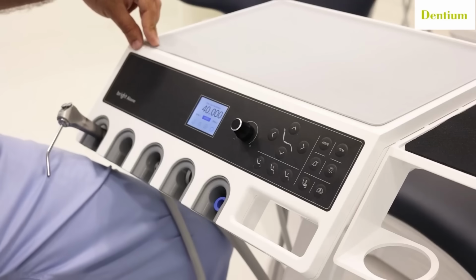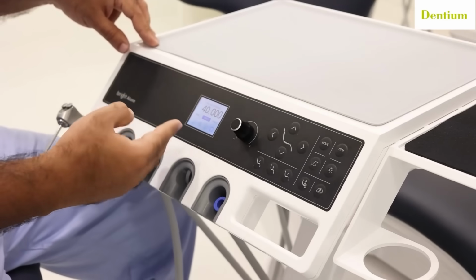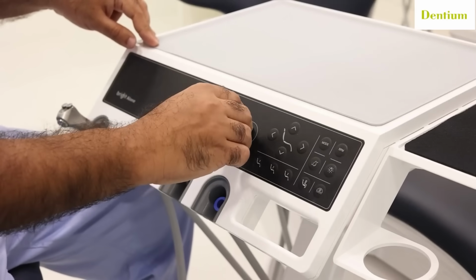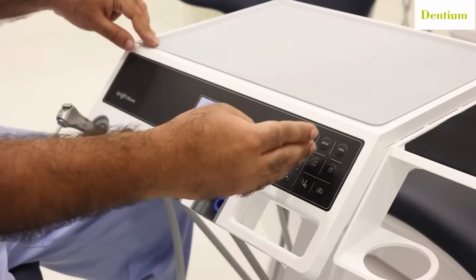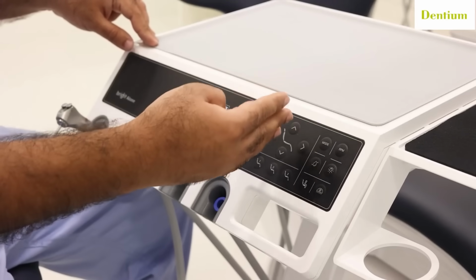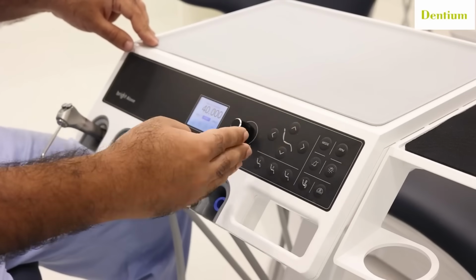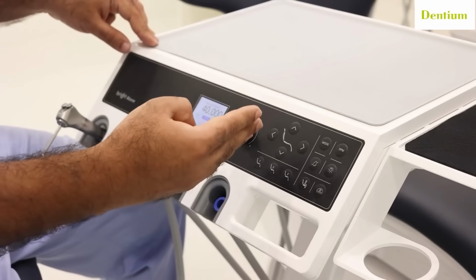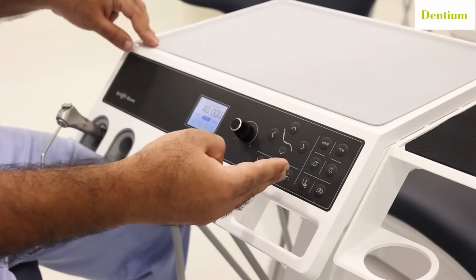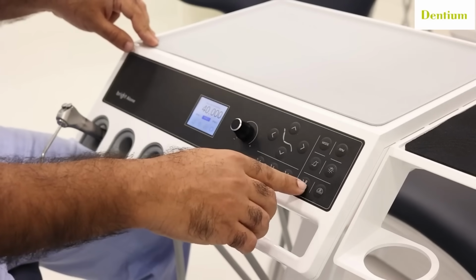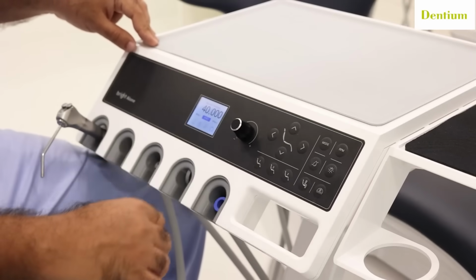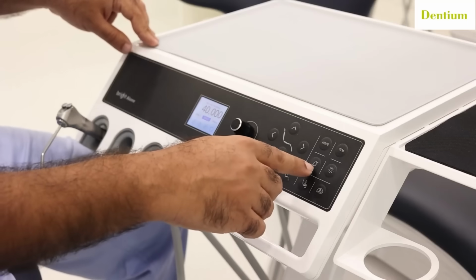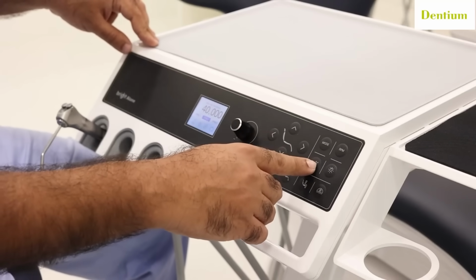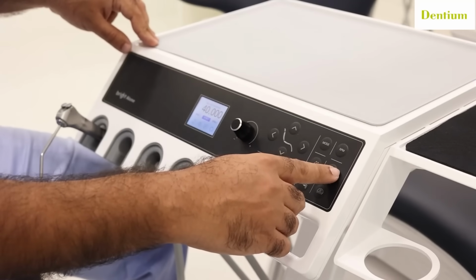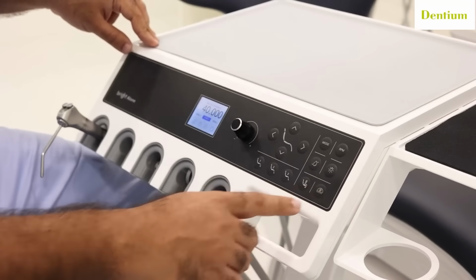So let's start with the control panel. The control panel starts with an LCD display, a knob to adjust your RPM, options given to move the chair up, down, back and front. There are 4 memory programs, where 1, 2 and 3 you can set the chair position, and the 4th is for the 0 position. Now if you can see, there are options to switch on and switch off the water supply, your light and your dental operative light.